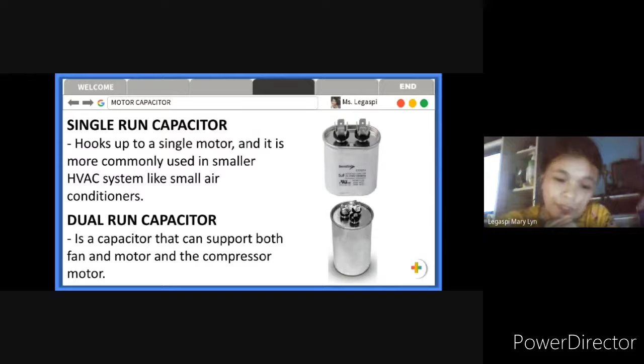So then the next type of run capacitor is dual run capacitor. It is a capacitor that can support both fan motor and the compressor motor. So dual run capacitor, ito is supported niya yung both motors, so no need nang i-short yung terminals niya na galing doon sa common line ng contactor which is yung power. Yung dual run capacitor, gaya ng sabi ko kanina, meron siyang 3 poles or 3 terminals, yung isa is for the common line, and the other one is for a fan, and the last one is for a compressor.